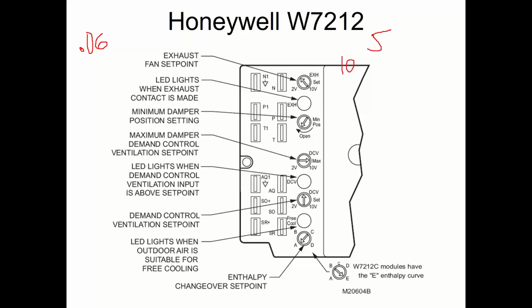So if I had 100 people in this space on a normal job, I would need 500 CFM of outside air for the people. And if I say it's 10,000 square feet, which I think is the same example we did last week, I would need 600 for the building, for building off-gassing. And combined, I would need 1,100 for a normal building. And 1,100 would go here on the minimum damper position setting. However, when I have DCV, that is not the case.